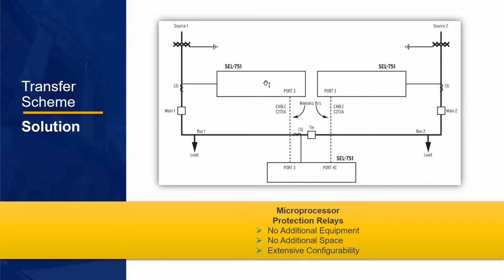Leveraging the configurability of the microprocessor relays, we were able to utilize the communication mirrored bits function of the SEL-751 to offer a sophisticated, secure, and automatic main transfer scheme. A few features we added were time delays to the trip and close push buttons to increase operator safety, indication and alarming when maintenance mode is enabled, and a permissive bypass when choosing to operate from the backup utility feed.